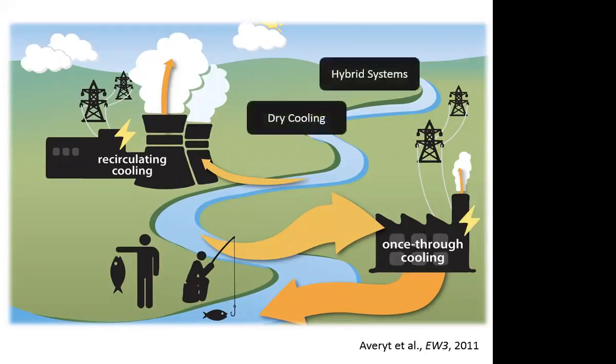There are two other types of cooling systems emerging, particularly as water issues become more important across the US and globally. The first is dry cooling, where instead of using water, you bring really cold, dry air into the power plant. The most optimal place to use this is somewhere like Siberia, and I'm not kidding - when ambient temperatures outside get to 90, 95 degrees Fahrenheit, dry cooling isn't efficient and you can't use it.